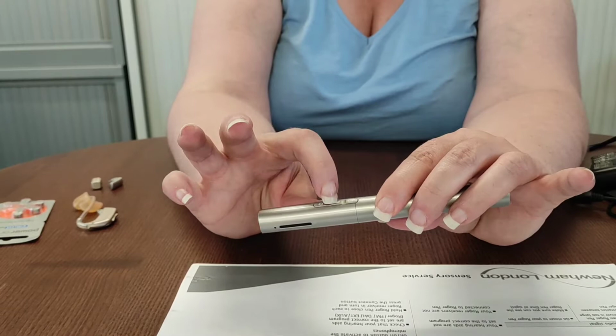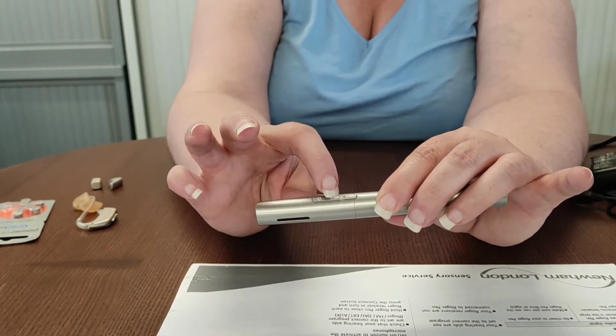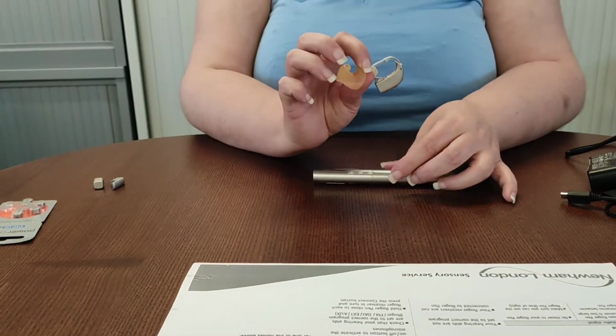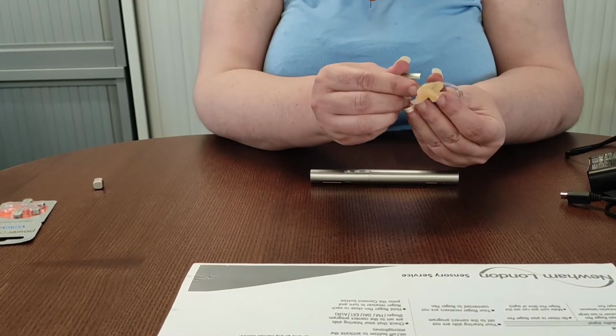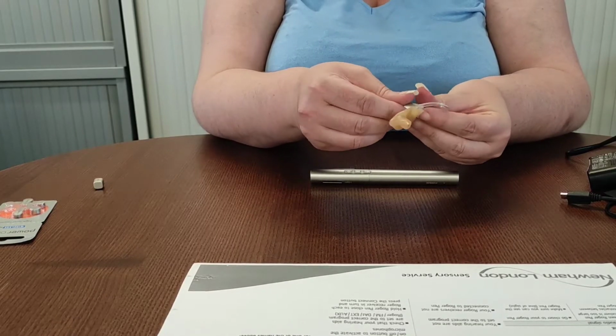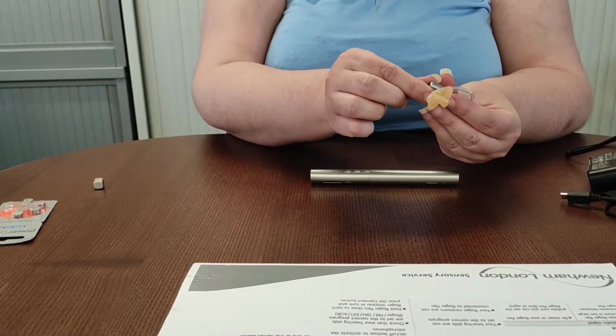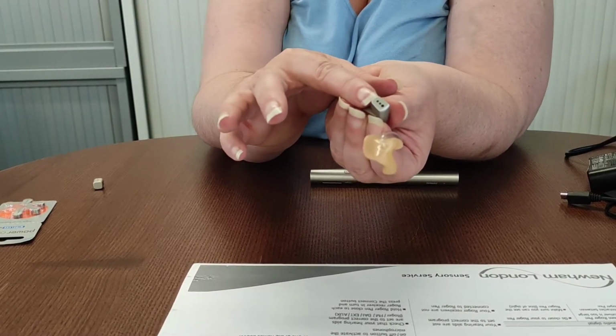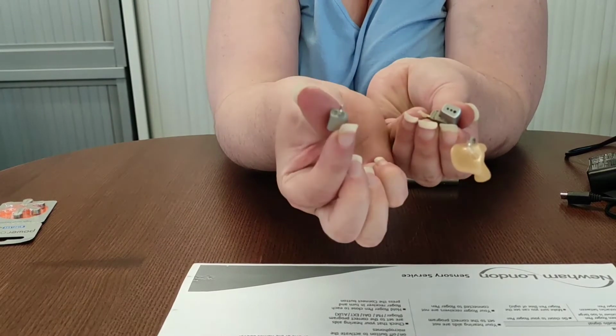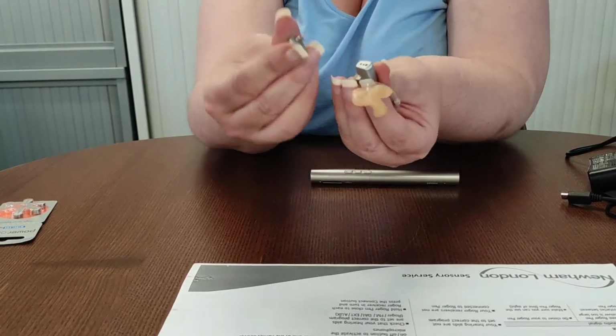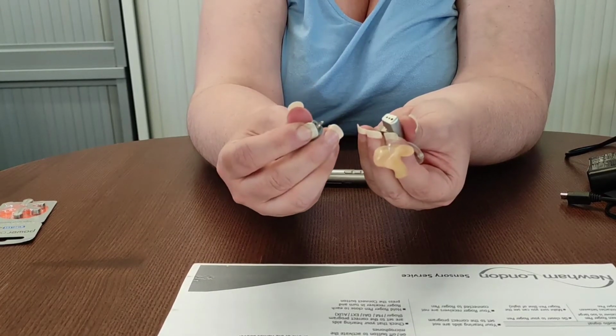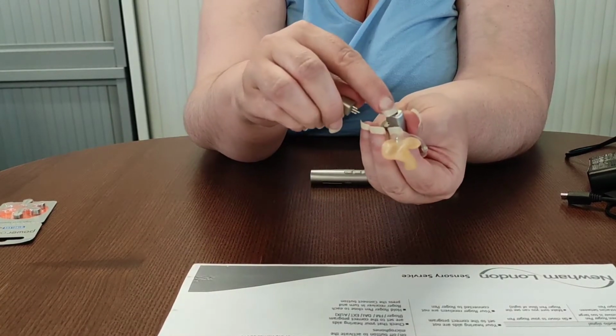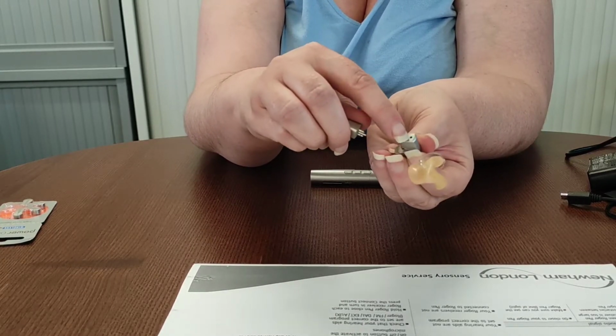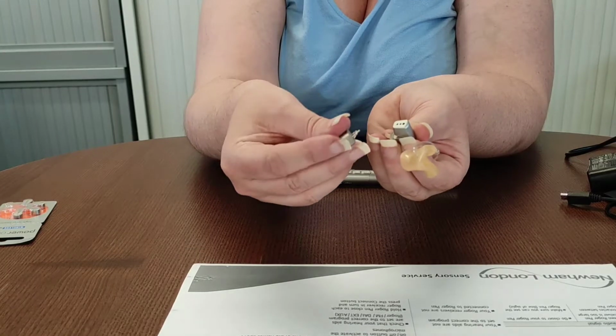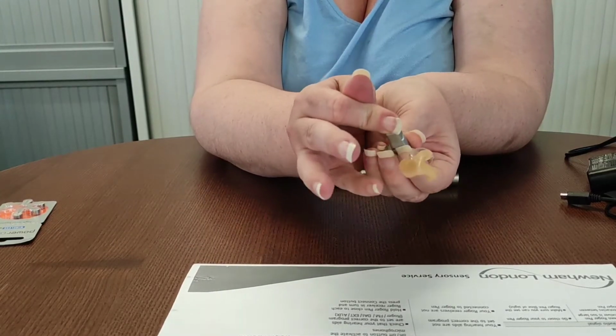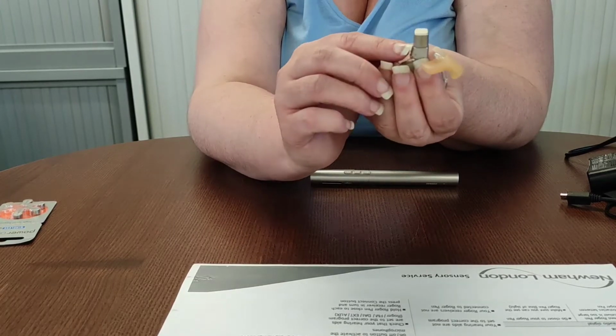We do have another button here next to it that I'm going to talk about, which is a connecting button. So for example, if a learner has hearing aids, they may have an audio shoe attached to the bottom, either as a battery compartment or as an additional section, like this one. On the bottom of that audio shoe are some small holes, and these are for the receiver that they will also be issued. This receiver, you have to be very careful because the prongs are different lengths and widths. So to match up the width of the prong with the deposit hole on the audio shoe, that's really important so we don't break it. So we have to make sure we hear it clip and that it will be a seal around the edge. There shouldn't be a gap.